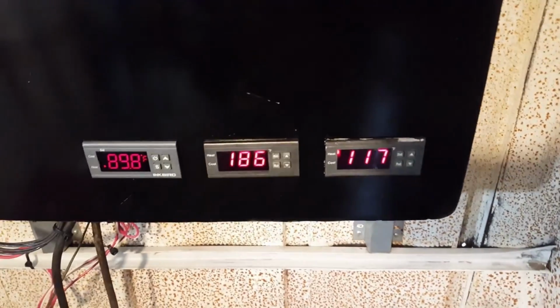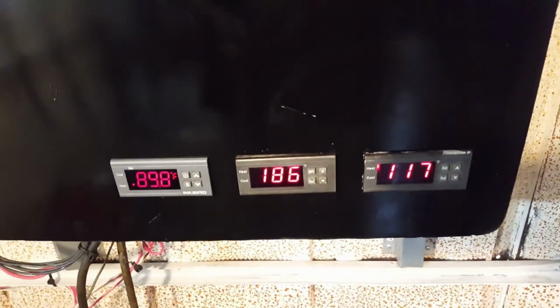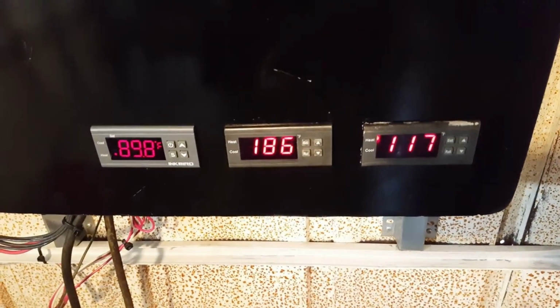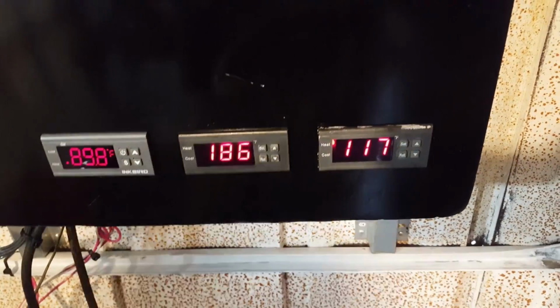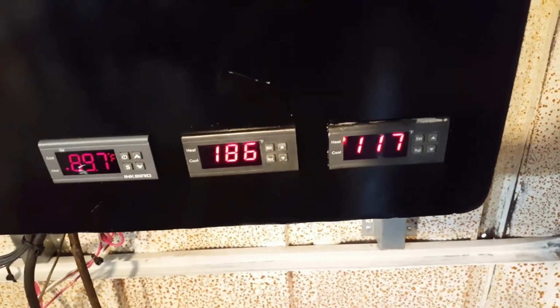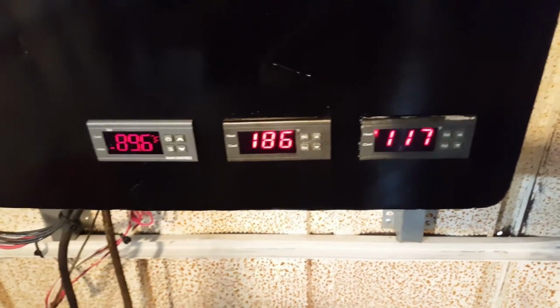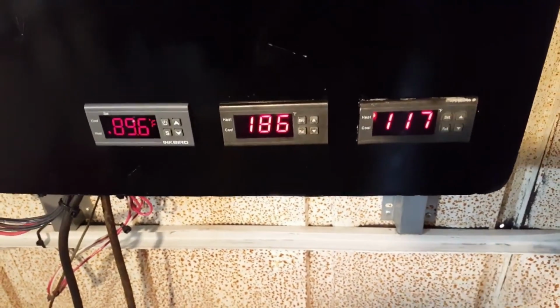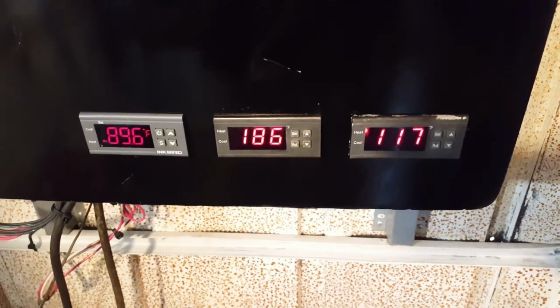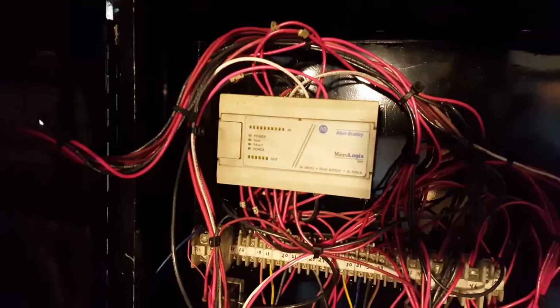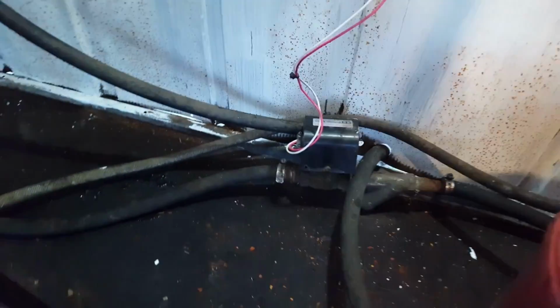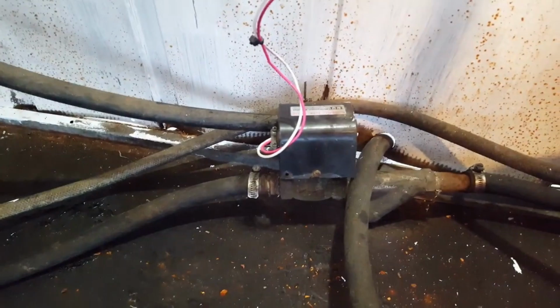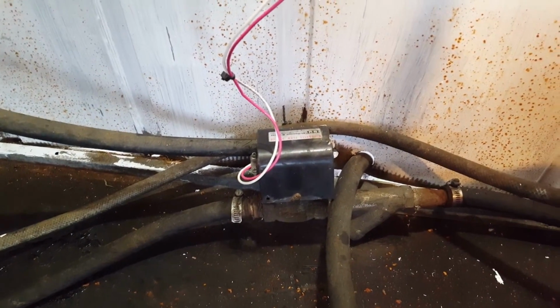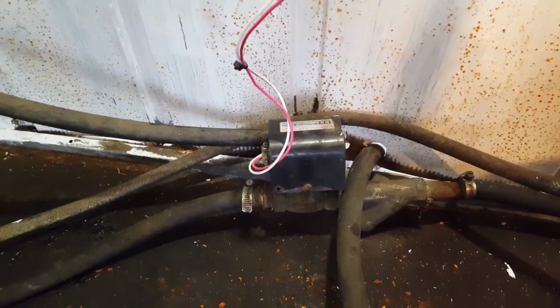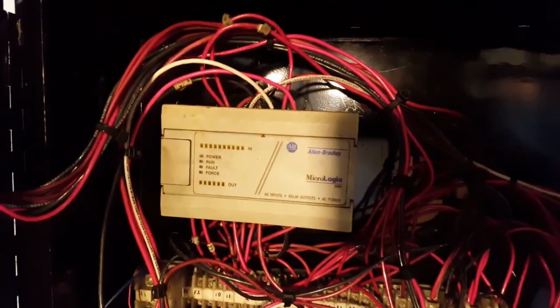Also, here's why I have it giving an input instead of not giving an input. If that temperature controller loses power and I don't know it, well, this thing's running without this over temp sensor. I don't want that. So if that temperature controller quits working, loses power, whatever, it'll lose the input and that'll shut everything down. Also, right here is a flow sensor. If my water pump quits or I get a hole and I lose water, that right there will tell the PLC, hey, we're not flowing water, shut it down. That's another input to the PLC.